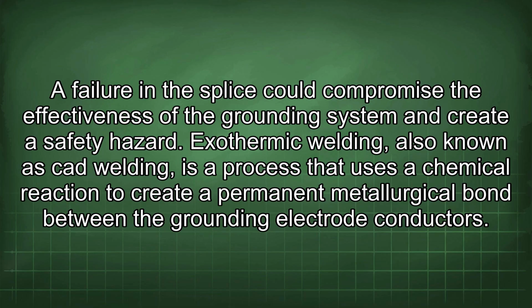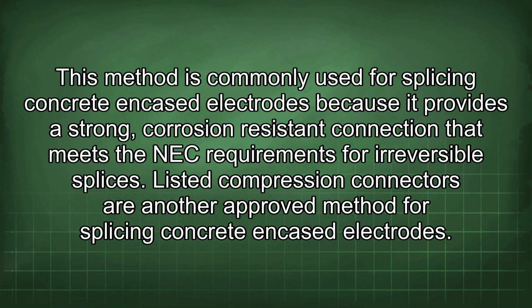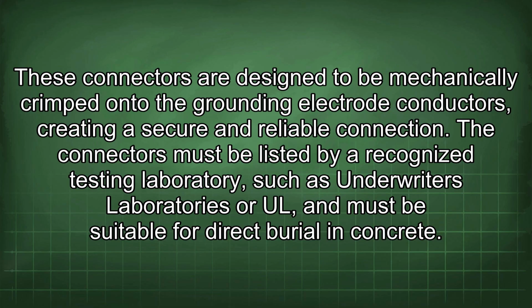Exothermic welding, also known as CAD welding, is a process that uses a chemical reaction to create a permanent metallurgical bond between the grounding electrode conductors. This method is commonly used for splicing concrete encased electrodes because it provides a strong, corrosion-resistant connection that meets the NEC requirements for irreversible splices. Listed compression connectors are another approved method for splicing concrete encased electrodes. These connectors are designed to be mechanically crimped onto the grounding electrode conductors, creating a secure and reliable connection.